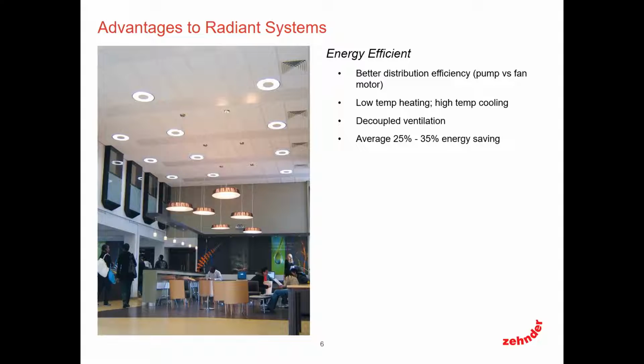In general, in most of the commercial spaces that we see, comparing the base building built to code-compliant commercial space and mechanical systems against the next building being built with all the energy efficiency in it, those typically I see somewhere between 25 to 35% energy savings. And that's taking, again, a holistic approach looking at the entire mechanical system.